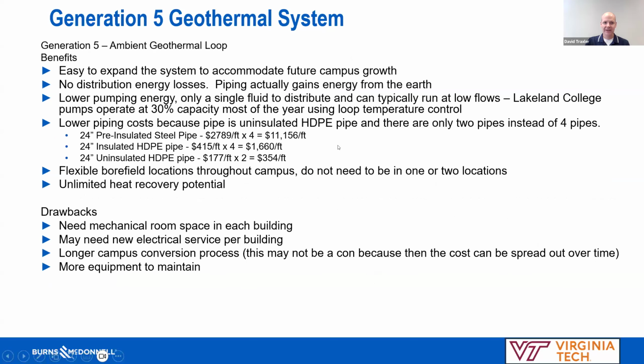In the ambient loop system, one of the key ingredients that's going to save money, which Carrie just referenced, is that the piping system is so much more affordable than insulated steel pipes, which are traditionally used for hot and chilled water systems. This is just from RS Means, which is an estimating handbook, and it doesn't include the trenching. But for 24 inches of uninsulated horizontal pipe, it's $177 a foot, or $354 per foot. For four 24-inch insulated steel pipes, it's $11,000 a foot. Well, it doesn't take long when you're at $11,000 a foot versus $200 to $400 a foot. Albeit it doesn't include the trenching, the traffic, and all the other things you have to go into. But there's a real significant cost savings there when you're putting in a district piping network.